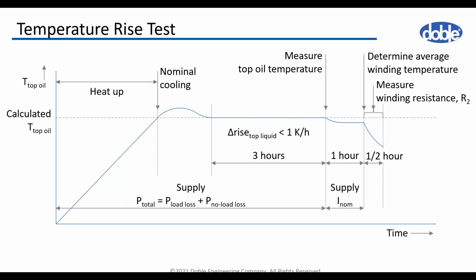So on the screen you can see a graph of how the top oil temperature would normally look during temperature rise test. At the first moment, we have increasing temperature, the heating up process, and after a moment of stabilization, we reach the flat part of the graph, at the end of which we can obtain the top oil temperature. Here we have a condition which we need to comply with: 3 hours with a difference of the top oil temperature of less than 1 Kelvin per hour.